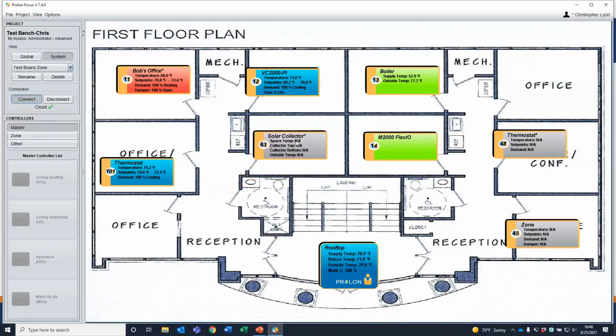One of the things you'll find is manufacturers like Carrier or Trane, they'll put these cards in that you can talk to. Well, Prolon is never going to talk to another system. What we are going to do is interact in the same manner a thermostat would. We'll give a signal that says, I would like first stage cooling, I would like the fan to run, I would like first and second stage heating. We're going to interact with it in that manner.